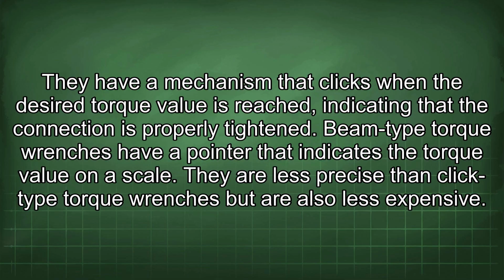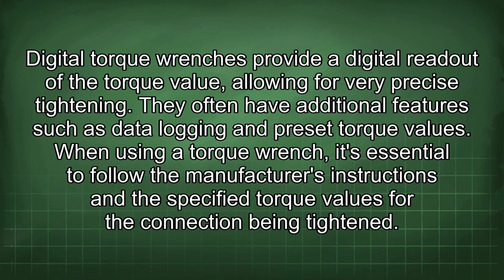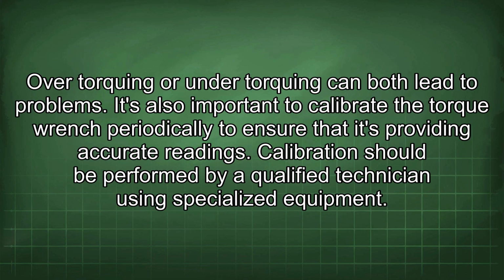Beam-type torque wrenches have a pointer that indicates the torque value on a scale. They are less precise than click-type torque wrenches but are also less expensive. Digital torque wrenches provide a digital readout of the torque value, allowing for very precise tightening. They often have additional features such as data logging and preset torque values. When using a torque wrench, it's essential to follow the manufacturer's instructions and the specified torque values for the connection being tightened. Over-torquing or under-torquing can both lead to problems. It's also important to calibrate the torque wrench periodically to ensure that it's providing accurate readings. Calibration should be performed by a qualified technician using specialized equipment.